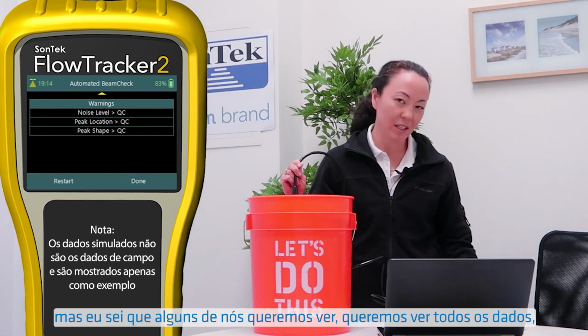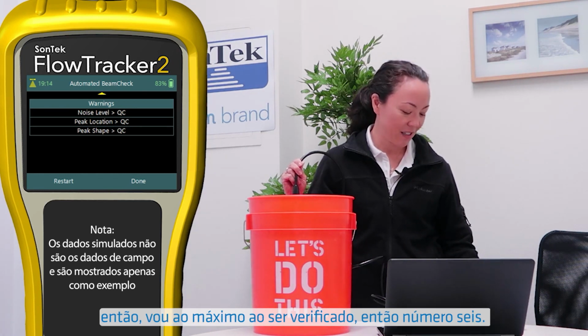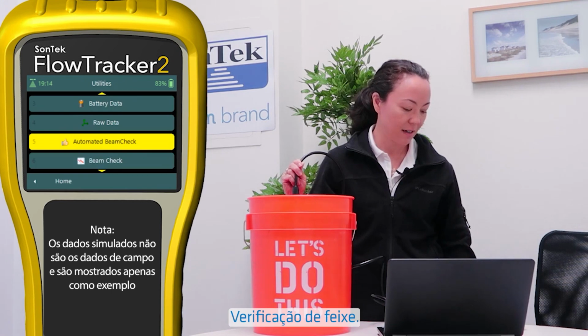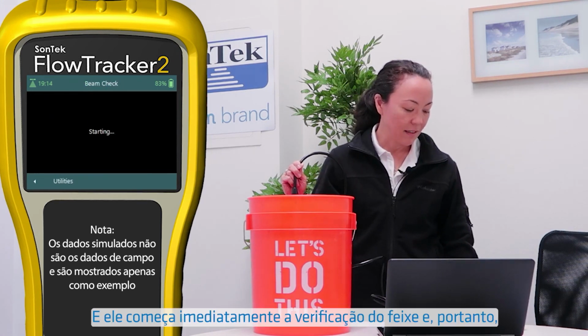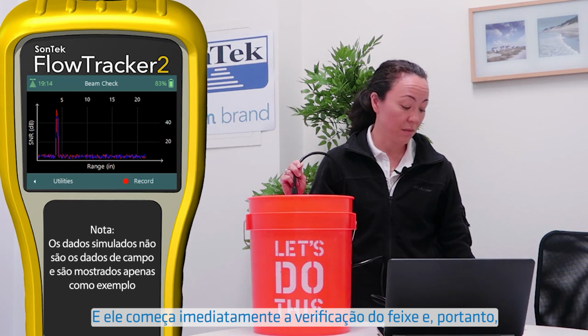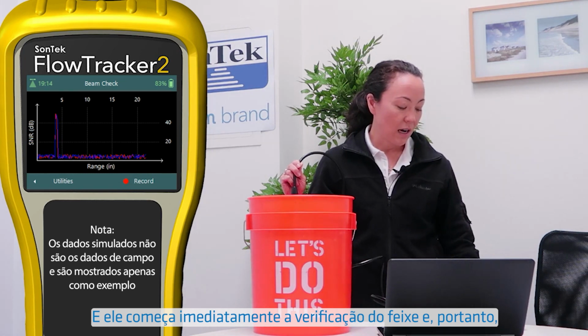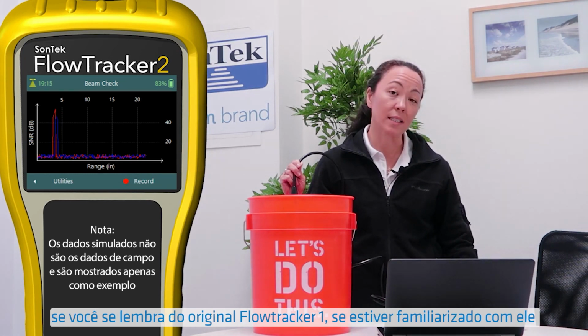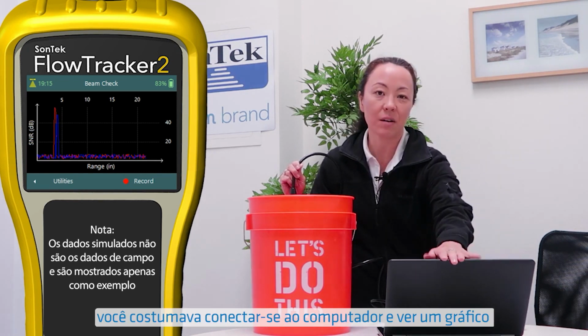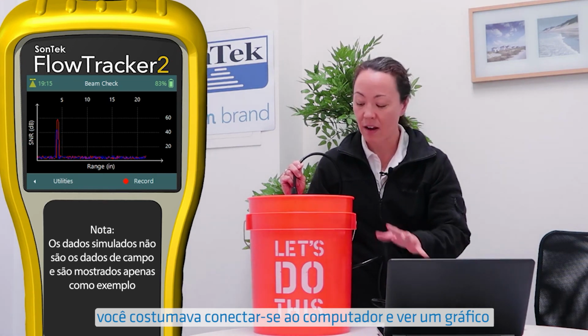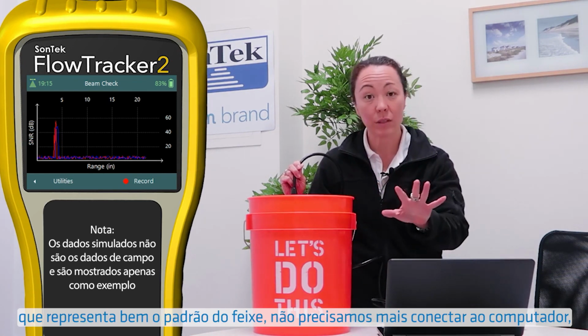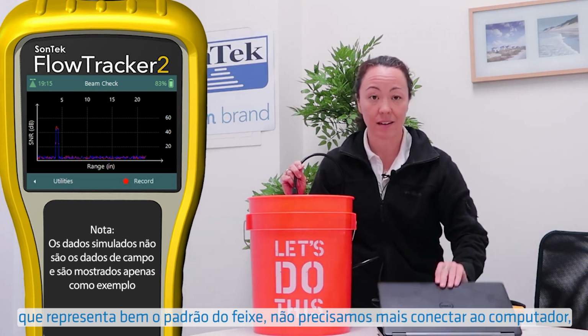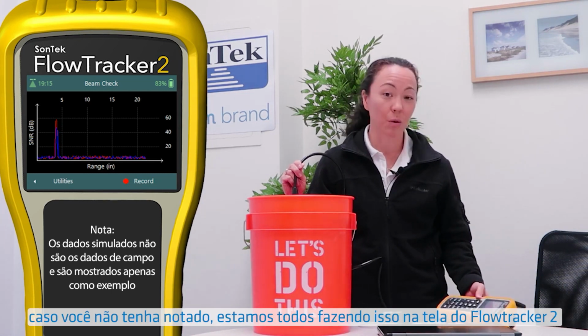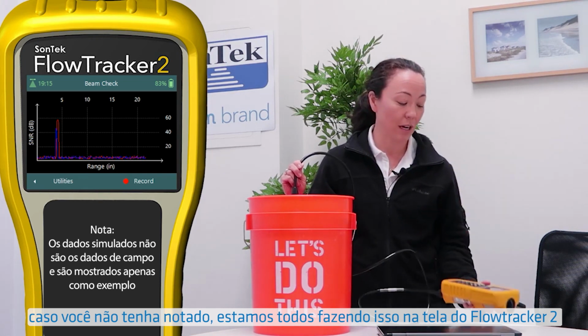But I know some of us, we want to see all that data, so I'm going to go to the full-on beam check. So item number 6, beam check. And it immediately starts into the beam check. And so if you remember the original FlowTracker 1, if you're familiar with it, you used to be able to connect on the computer and see a graph that represents the beam pattern. Well, you don't have to connect to the computer anymore, if you haven't noticed. We're all doing this in the screen of the FlowTracker 2.